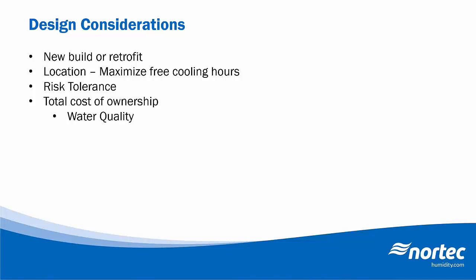The second is location of the data center. So determining whether using direct evaporative cooling is a cost-effective and feasible solution, or possibly maybe an indirect solution might work better depending on the outside air conditions. As I mentioned, the Green Grid has a great online calculator that can help you estimate the hours of free cooling as well as estimated cost savings based on average weather data for a specific location. So be sure to check that out if you are interested. The third here is risk tolerance. So how risk averse is the data center owner? Is the owner willing to open up the allowable range for temperature and humidity to really take advantage of that free cooling effect?